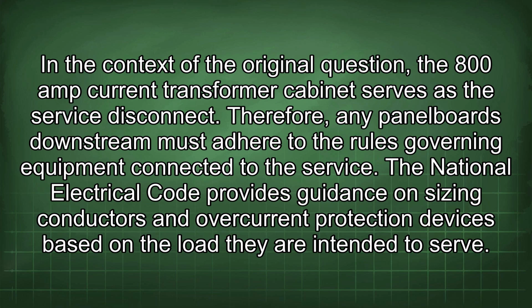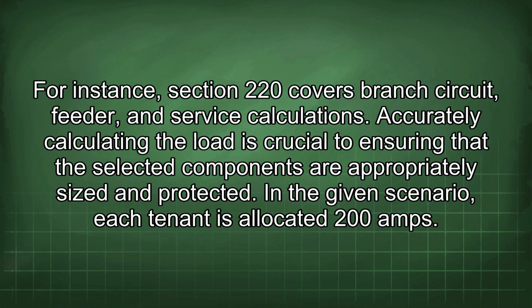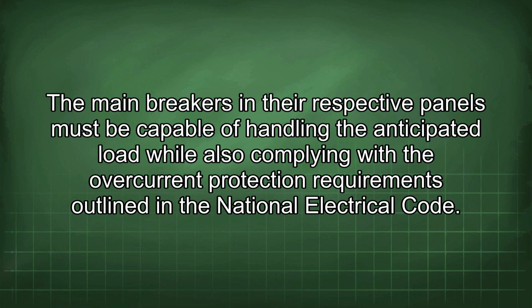The National Electrical Code provides guidance on sizing conductors and overcurrent protection devices based on the load they are intended to serve. For instance, Section 220 covers branch circuit, feeder, and service calculations. Accurately calculating the load is crucial to ensuring that the selected components are appropriately sized and protected. In the given scenario, each tenant is allocated 200 amps. The main breakers in their respective panels must be capable of handling the anticipated load while also complying with the overcurrent protection requirements outlined in the National Electrical Code.